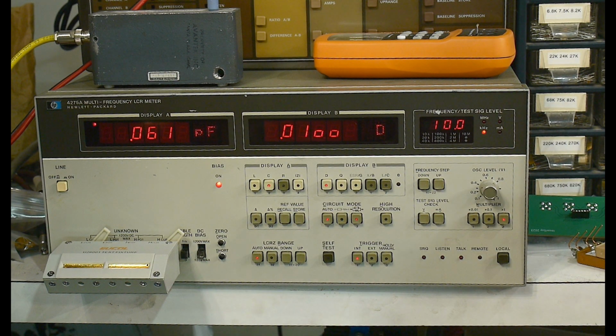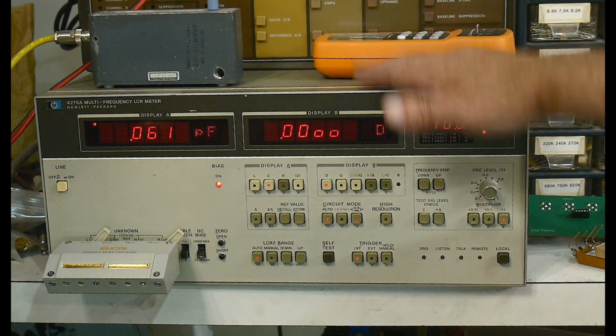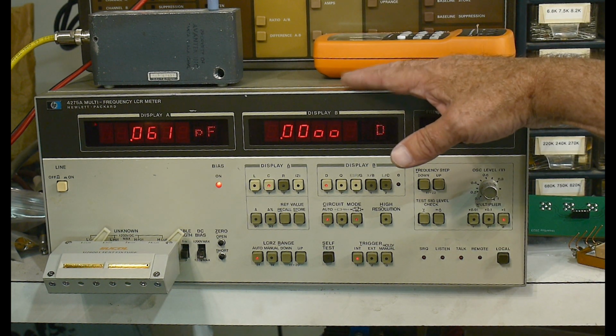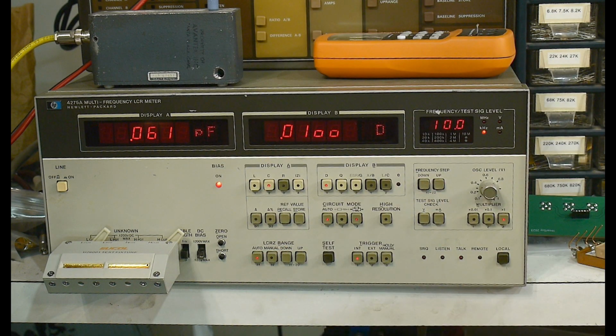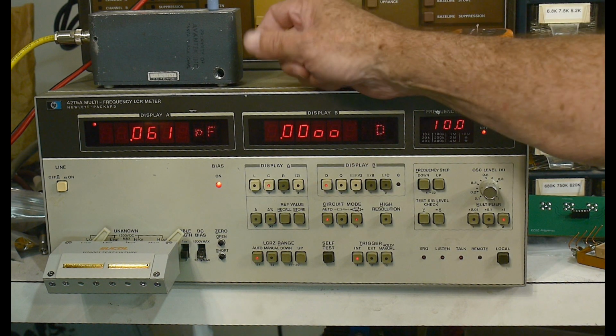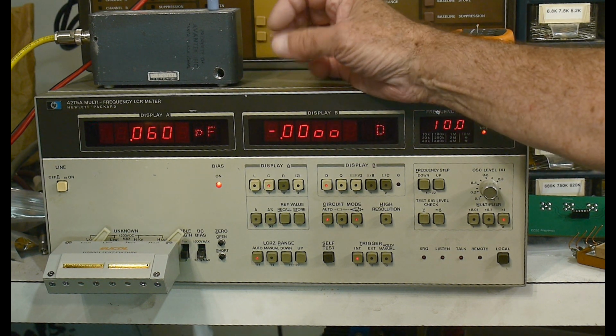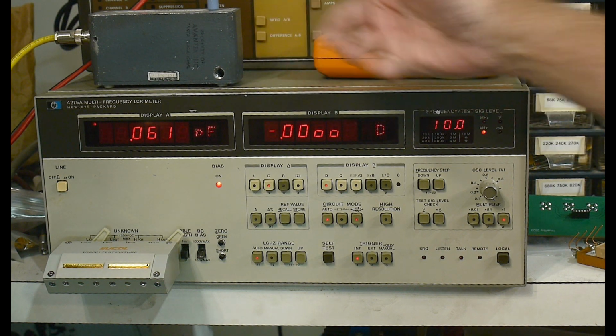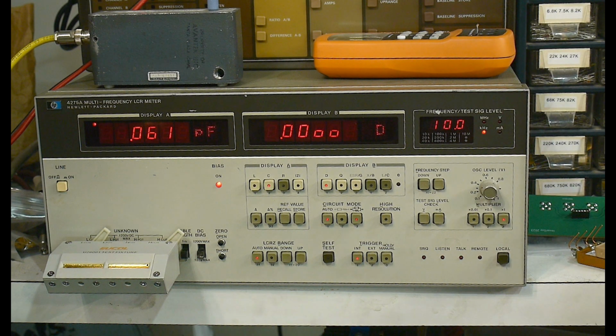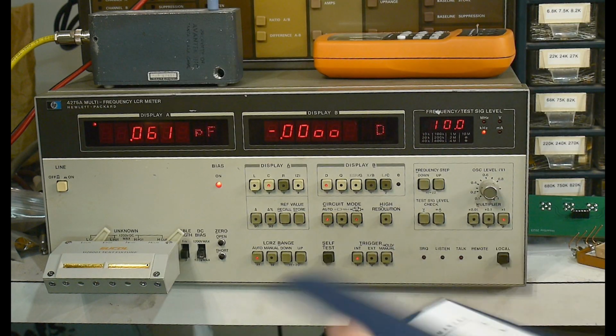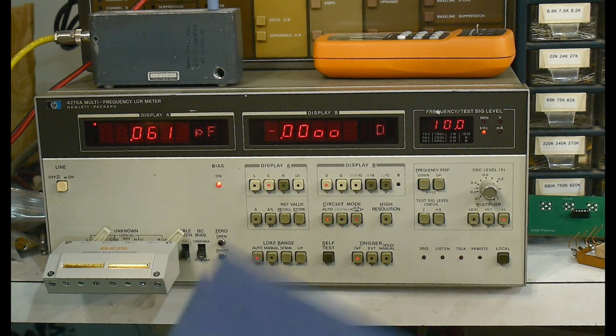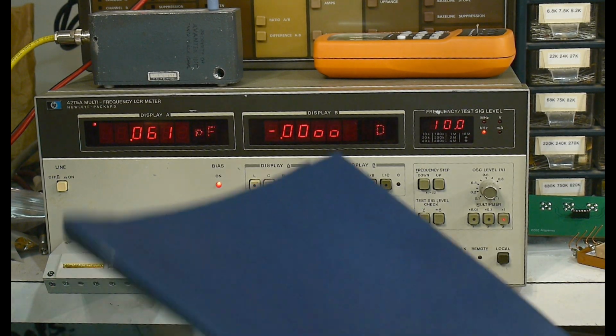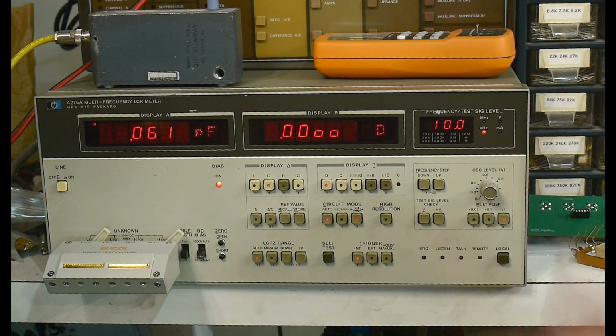One of the things I had to do was create some secondary standards. As part of the calibration routine of this instrument, you put in known resistances and you turn potentiometers inside. There's 4 ranges, and you adjust those 4 ranges. It's all in the service manual. There's a lengthy procedure of how to calibrate this thing in the service manual. And there's various versions of the service manual from 1981 to 1991, so you can take a look at each one and see what the differences are. I use the 1991, figure it's best.